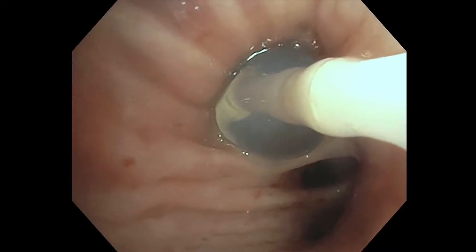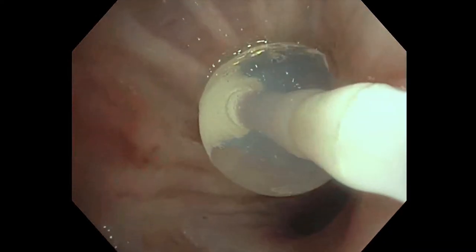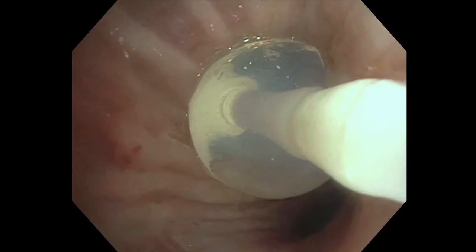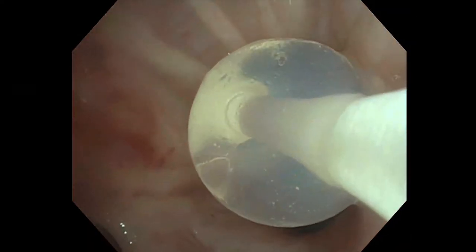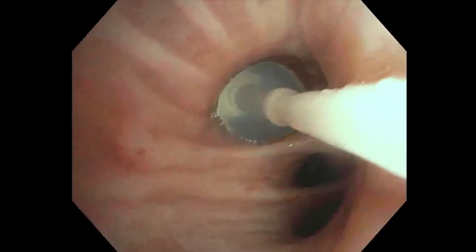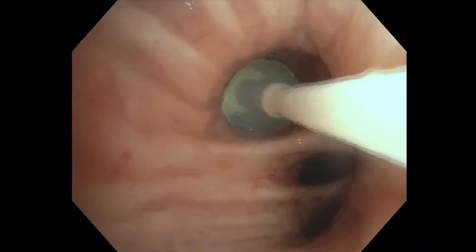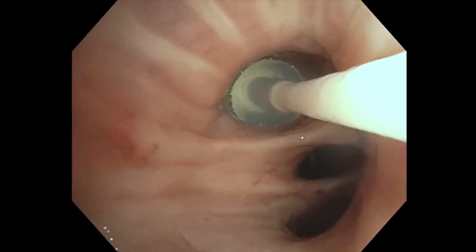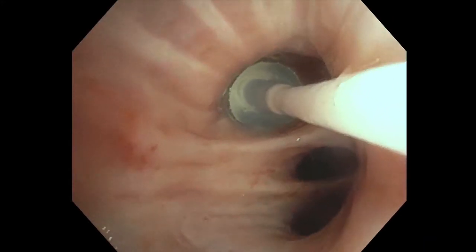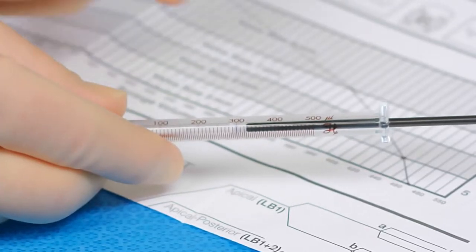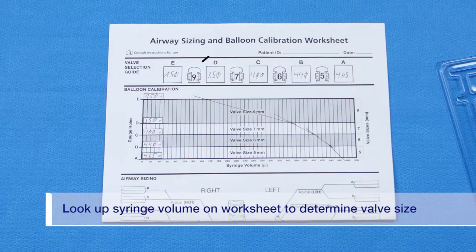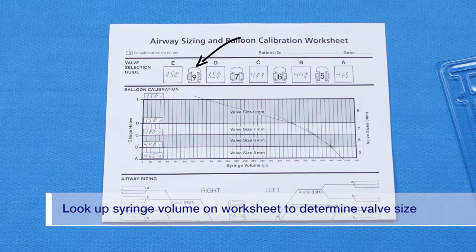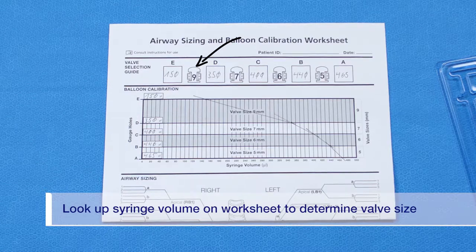The bronchoscopist should feel a slight tug when moving the catheter back and forth to assure a good fit, taking care not to over or under inflate, as this can result in the selection of an improper valve size. Using the worksheet that was filled out during balloon calibration, look up the syringe volume on the worksheet table and select the indicated valve size.